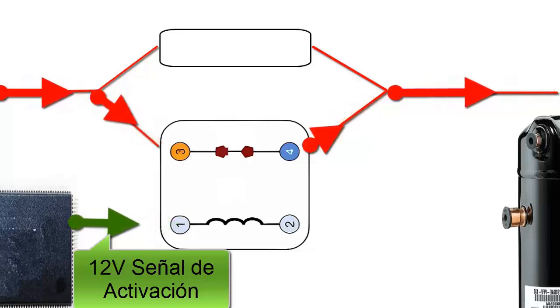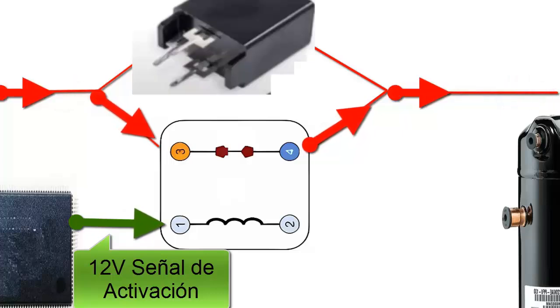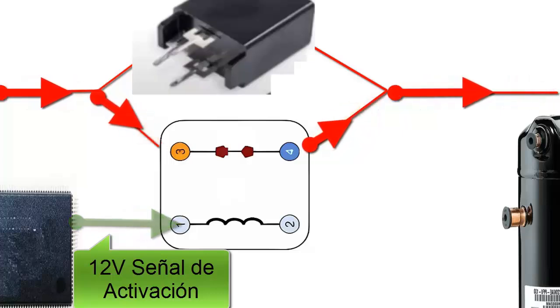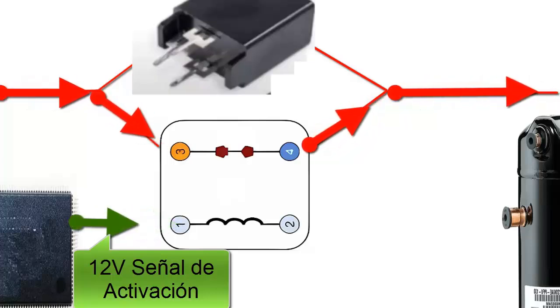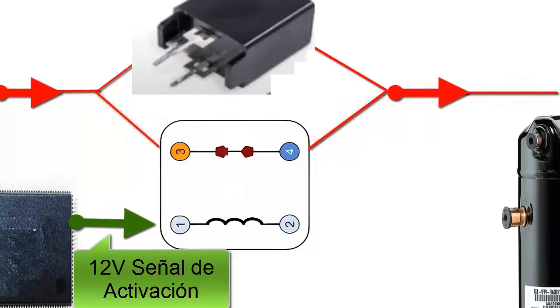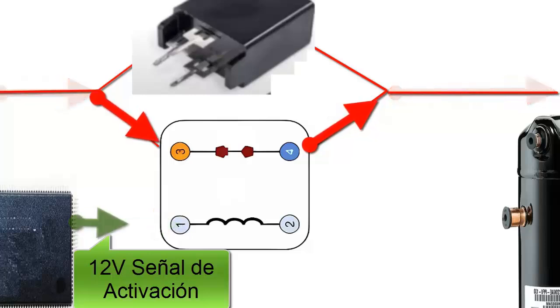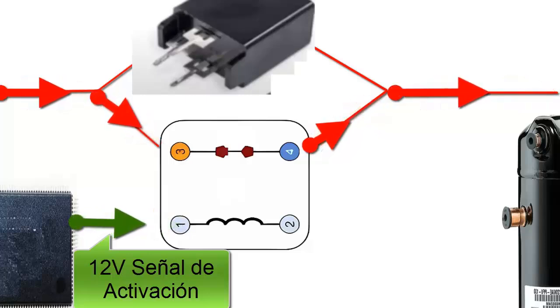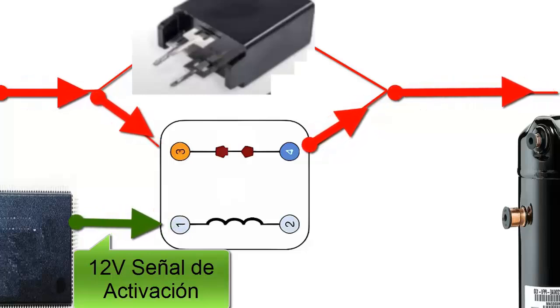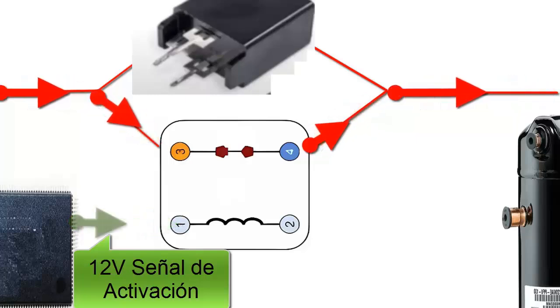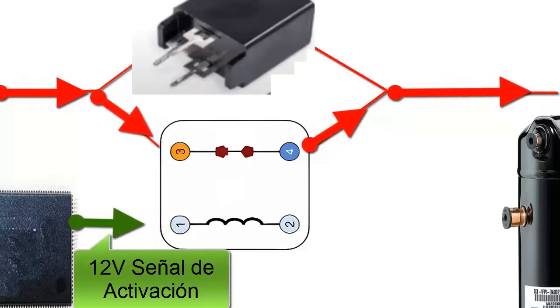The PTC resistor is designed to work as a safety system against excessive current consumption. If the PTC resistor is always activated, its temperature will increase. This indicates that the electronic board has not sent safe current values, which is why the contactor is not activated, or it could also signal issues with the contactor.